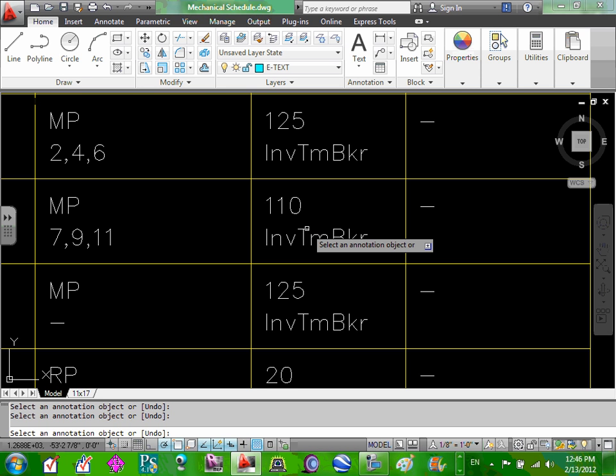You can, but you oversize. The reason why we have the overcurrent protection device much larger, Dustin, than the conductor is because of the inrush of the equipment. Mechanical equipment and motors have an inrush. That's why we always oversize the overcurrent protection device to handle the inrush. But the cable does not need to be sized to handle the inrush. Cables can handle the inrush without oversizing them. So that's why you don't have to match.